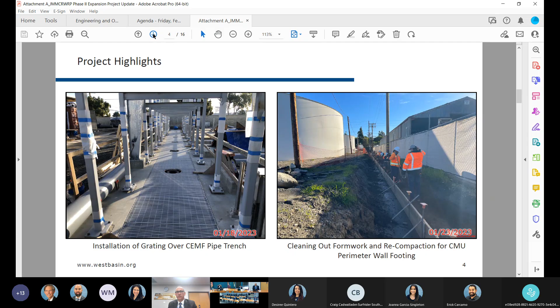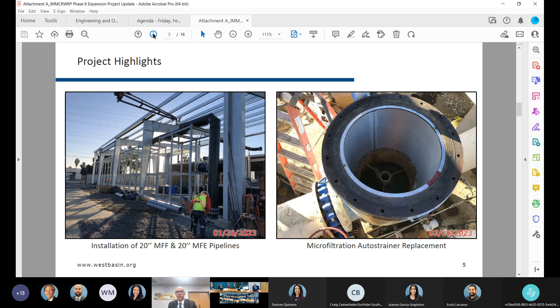On the left-hand side, you can see the CMF structure. A significant amount of the above-grade piping is being installed, and those two big pipelines shown are the feed piping and the filtrate piping. On the right-hand side, another accomplishment from the past month or so has been the replacement of our auto strainers. With the new modules coming in, the new auto strainer requirement is 200 microns, previously 500 microns, so it should filter out a lot more of the particulates. That's the newly installed auto strainer on the right side. Next slide, please.